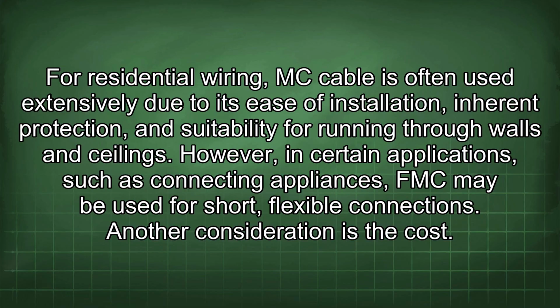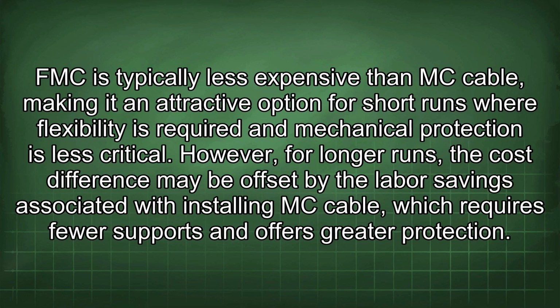Another consideration is the cost. FMC is typically less expensive than MC cable, making it an attractive option for short runs where flexibility is required and mechanical protection is less critical. However, for longer runs, the cost difference may be offset by the labor savings associated with installing MC cable, which requires fewer supports and offers greater protection.